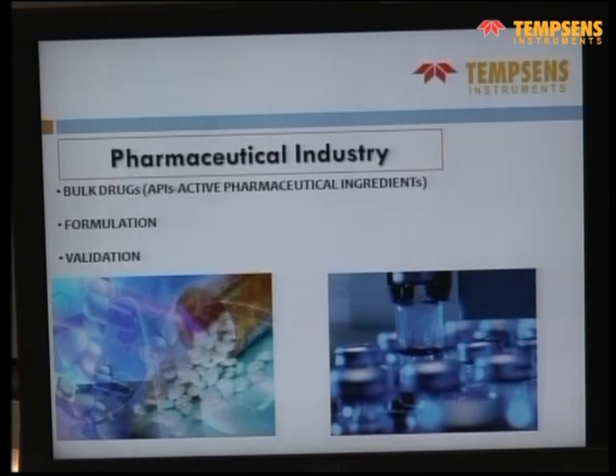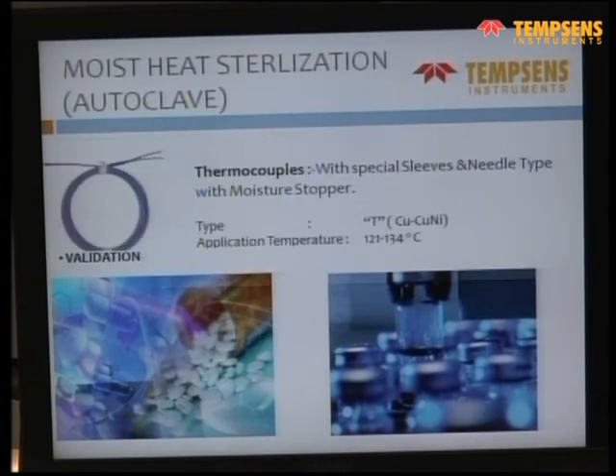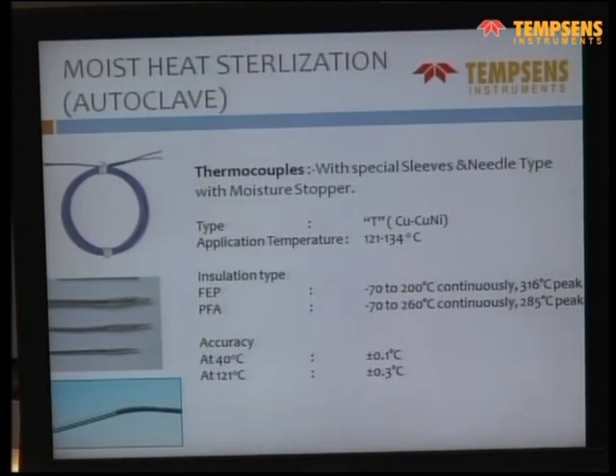In pharma industry, there are various applications. So they are normally low temperature applications. Normally in pharma industries, either we use a T-type thermocouple or an RTD, and the J-type thermocouple is normally used in the plastic industry. In case of pharma industry, thermocouples are used in autoclave application for bulk drugs. So here the main requirement is through the sensor.